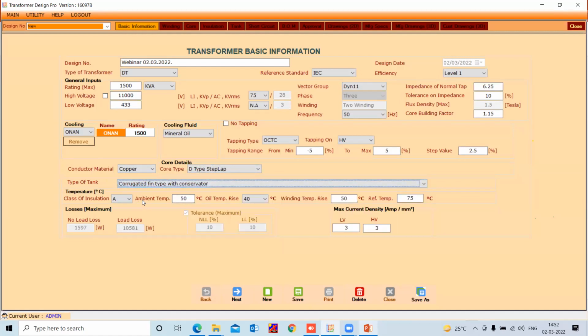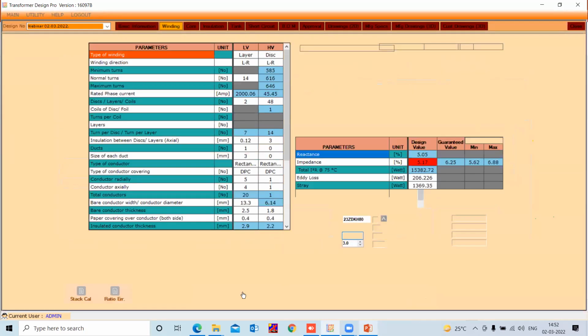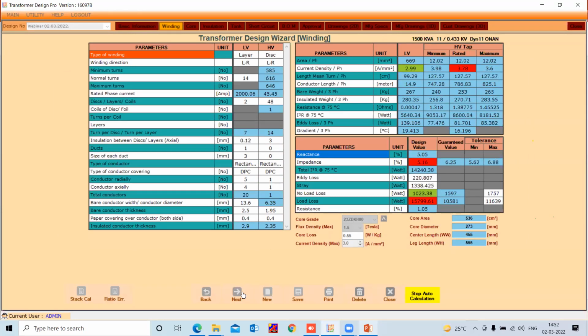And then the class of insulation A, the ambient temperature maximum chosen as 50 degrees, the oil temperature rise, winding temperature rise, the reference temperature, and the maximum current density at which you expect the software to design the transformer. Now, friends, with this, we can go for the next button at the bottom, and this will immediately take you to the winding card of the transformer.